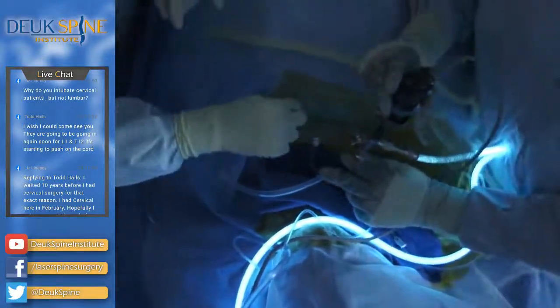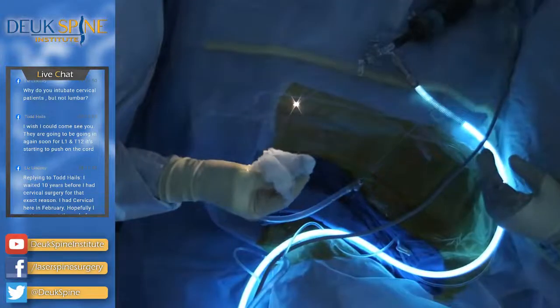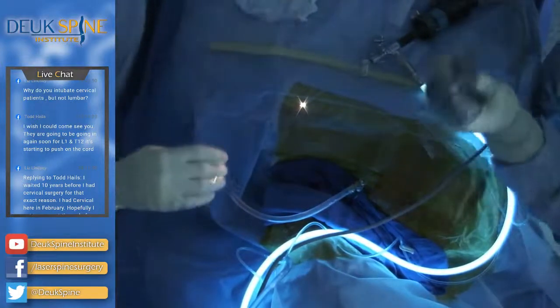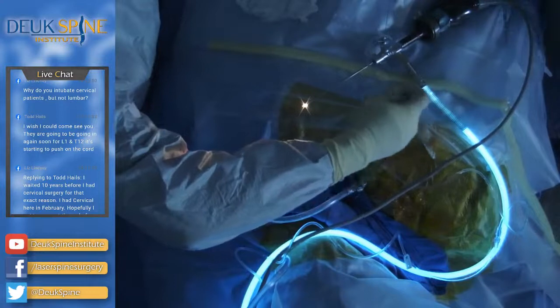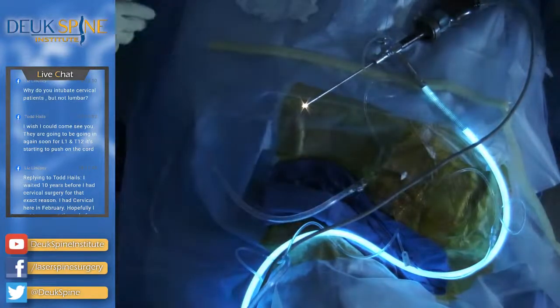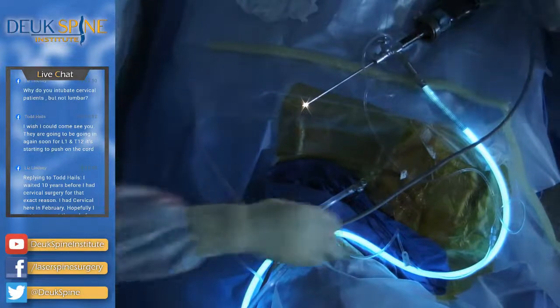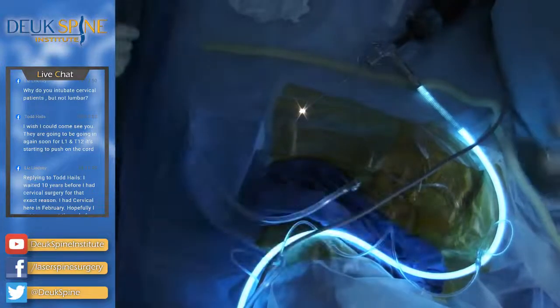I'll tell you a funny story. It's not funny actually, but it's upsetting. When we built our surgery center, we wanted to have these 72-inch monitors inside the operating room. So I told my IT guy, go to Best Buy or BJ's and buy the 72-inch monitors. So we did, and we paid $500 per TV, and we've got two of them in here, right? $500, no joke. Then the inspector came and said, what is that? You're not allowed to have that 72-inch TV from BJ's or Best Buy here. You need a medical-grade television. Medical-grade, that's the word. So we looked up, and guess what? $10,000 per television. I spent $20,000 for two of those TVs.